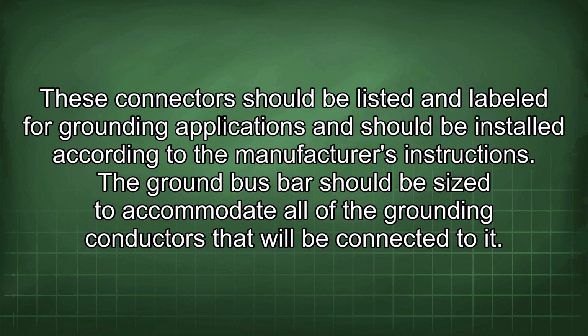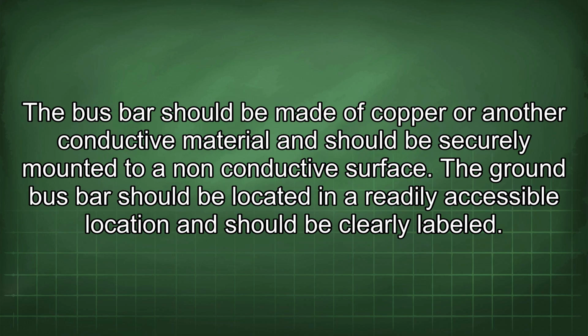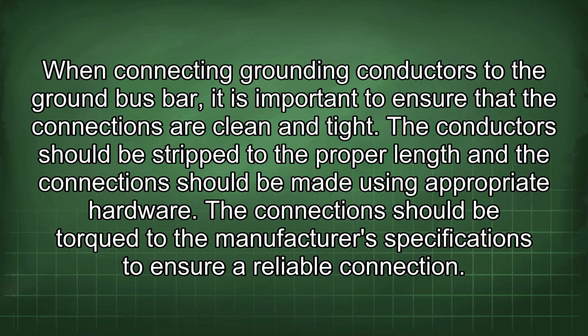The ground bus bar should be sized to accommodate all of the grounding conductors that will be connected to it. The bus bar should be made of copper or another conductive material and should be securely mounted to a non-conductive surface. The ground bus bar should be located in a readily accessible location and should be clearly labeled. When connecting grounding conductors to the ground bus bar, it is important to ensure that the connections are clean and tight. The conductors should be stripped to the proper length and the connections should be made using appropriate hardware. The connections should be torqued to the manufacturer's specifications to ensure a reliable connection.